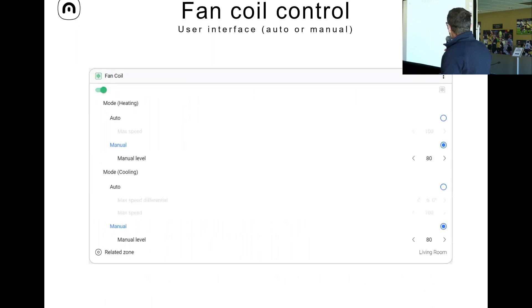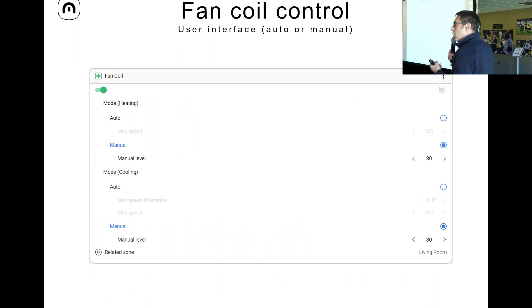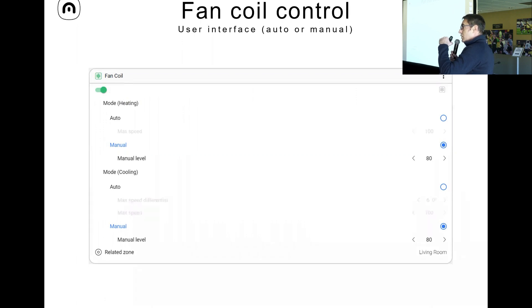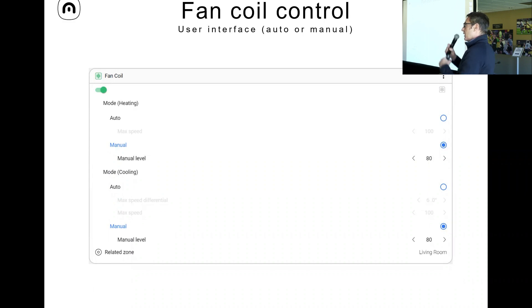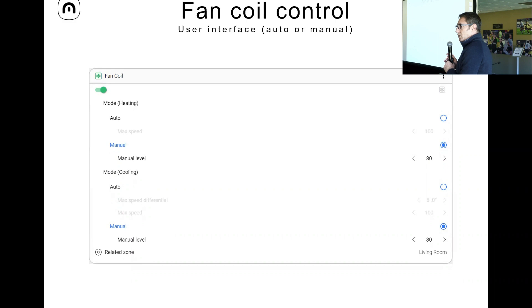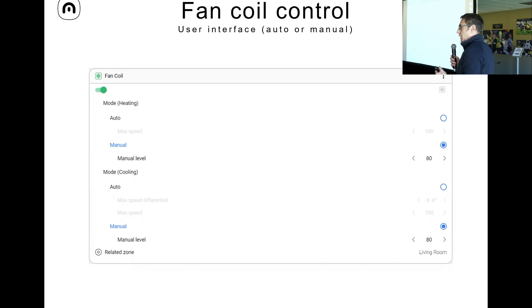Here is how the fan coil interface looks. You can set the fan coil to manual and set the speed. If you have a modulating fan coil, you can set the speed and voltage — say from 2 to 8 volts, so 20 to 80 percent — and modulate between those max values. You can set your maximum speed, for example 80 percent, because you don't want too much noise from the fan coil.